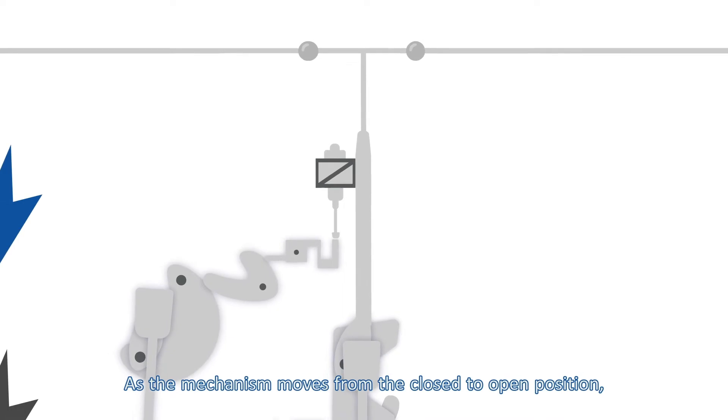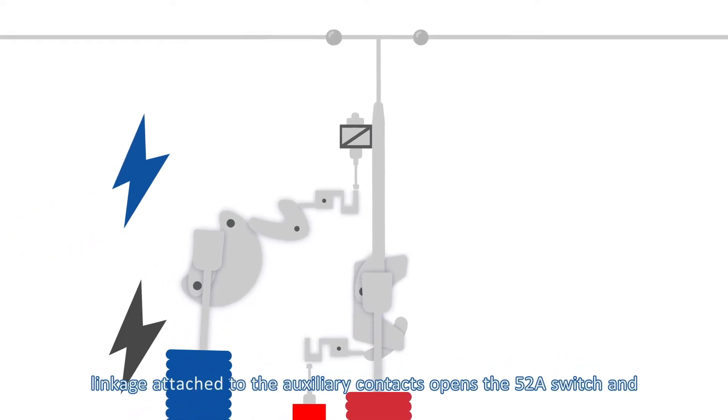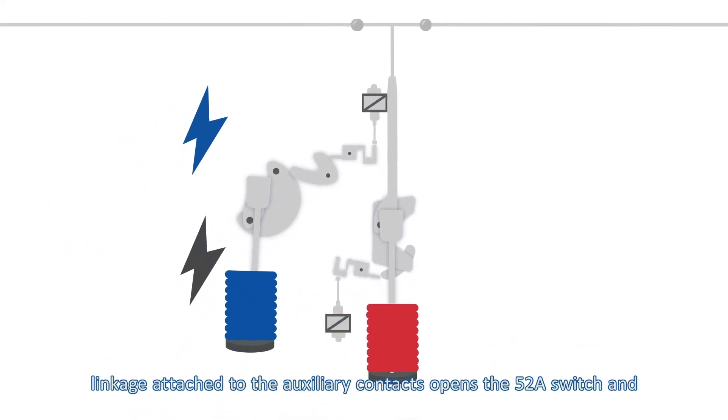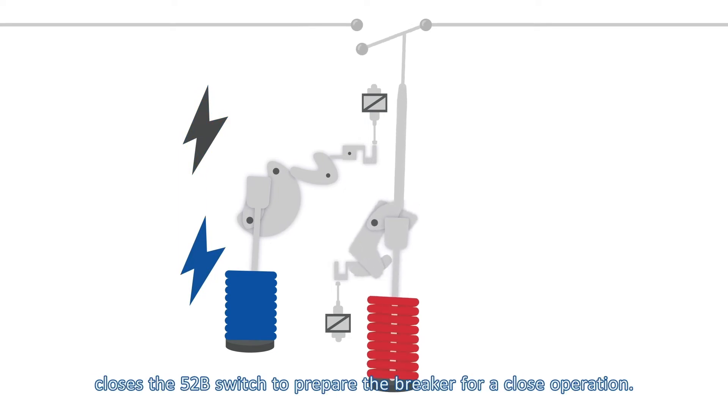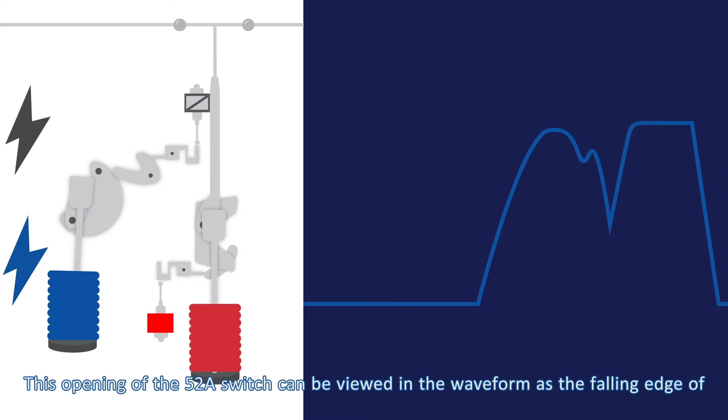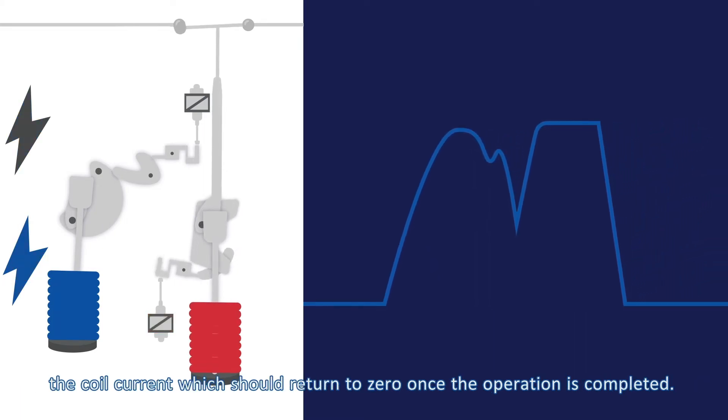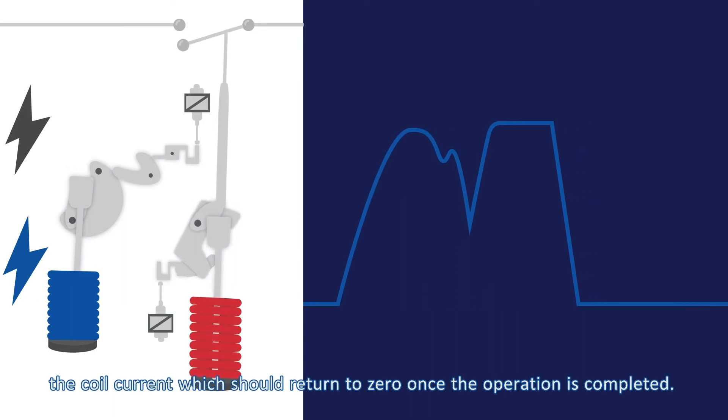As the mechanism moves from the closed to open position, linkage attached to the auxiliary contacts opens the 52A switch and closes the 52B switch to prepare the breaker for a closed operation. This opening of the 52A switch can be viewed in the waveform as the falling edge of the coil current, which should return to zero once the operation is completed.